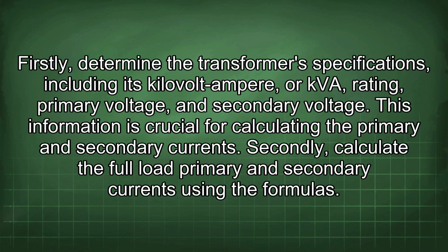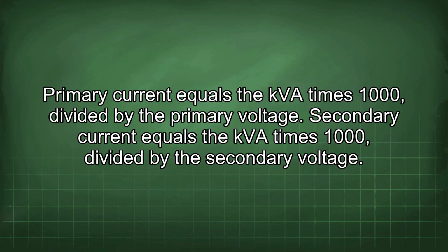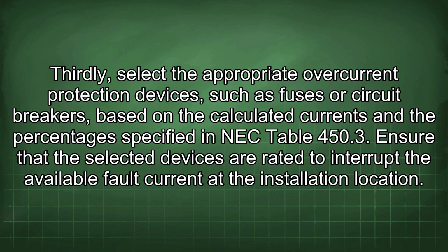Firstly, determine the transformer specifications, including its kilovolt ampere, or kVA, rating, primary voltage, and secondary voltage. This information is crucial for calculating the primary and secondary currents. Secondly, calculate the full load primary and secondary currents using the formulas. Primary current equals the kVA times 1000 divided by the primary voltage. Secondary current equals the kVA times 1000 divided by the secondary voltage. Thirdly, select the appropriate overcurrent protection devices, such as fuses or circuit breakers, based on the calculated currents and the percentages specified in NEC Table 450.3. Ensure that selected devices are rated to interrupt the available fault current at the installation location.